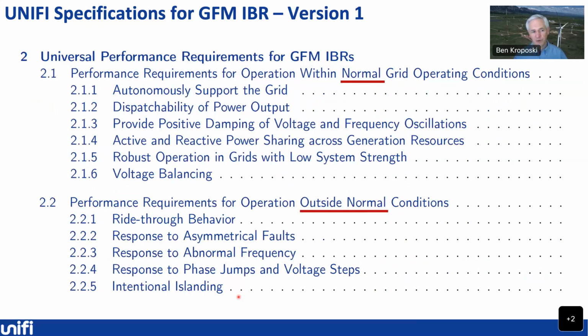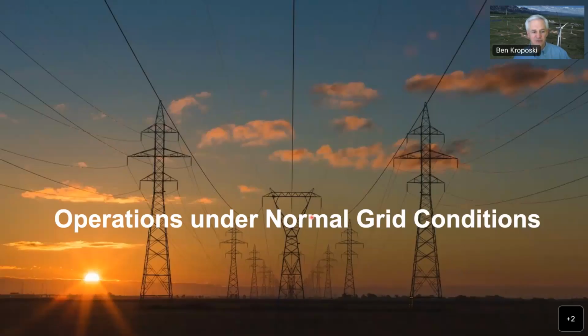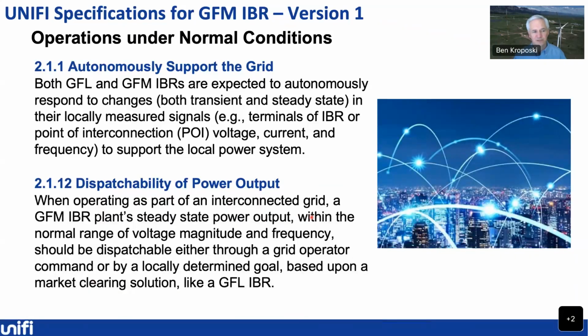Now, we split up both a set of universal performance requirements that every grid forming inverter should have and some of what we might call grid forming plus. We'll get into those in a second, but first let's cover the universal performance requirements. We want to understand what they can do under both normal and abnormal grid operating conditions. So first off, operating under normal conditions, we want to make sure that these grid forming inverters autonomously support the grid. This is also a capability that you'll see in grid following inverters, but we wanted to make sure that people realized that both of these technologies can do autonomous support, meaning they're going to locally measure voltage and current, and they're going to be injecting power or maintaining voltage, depending on what type of setup they have, autonomously.